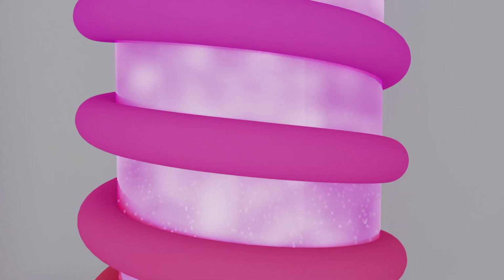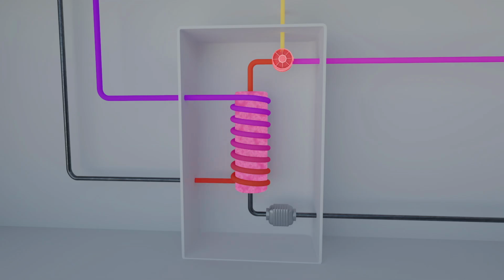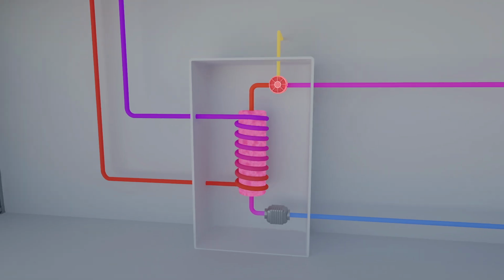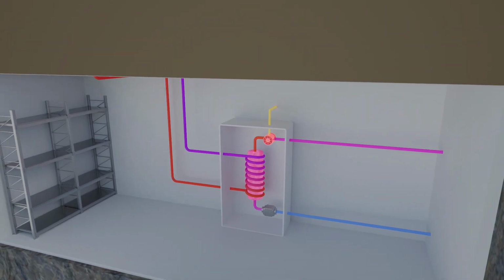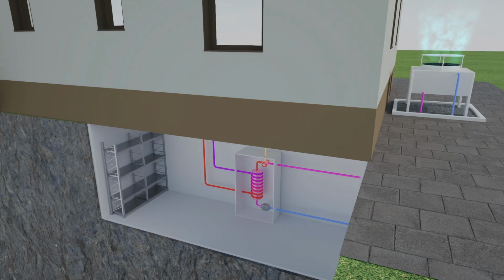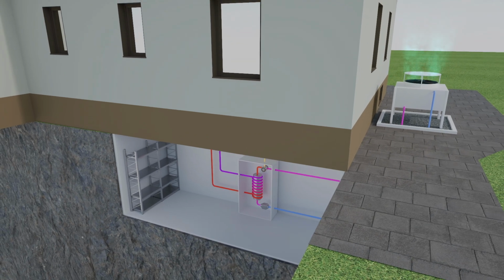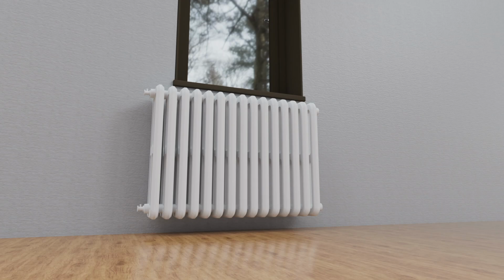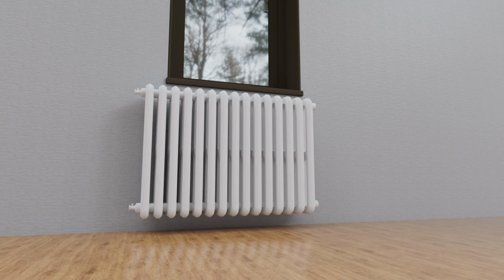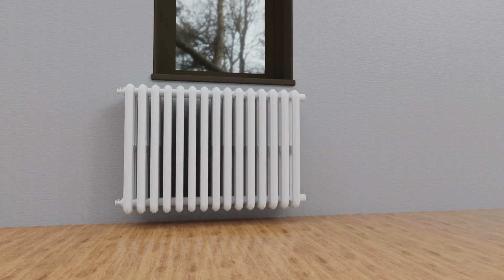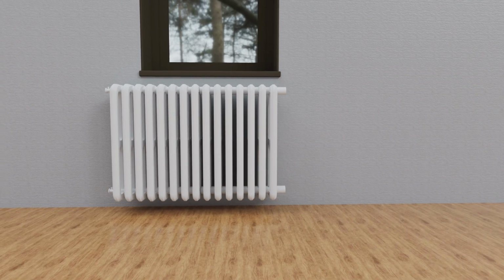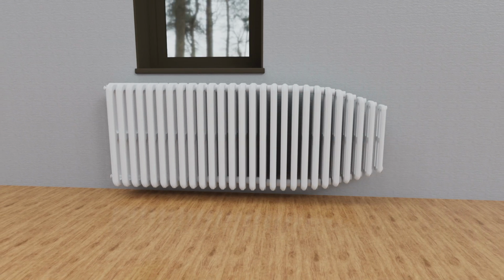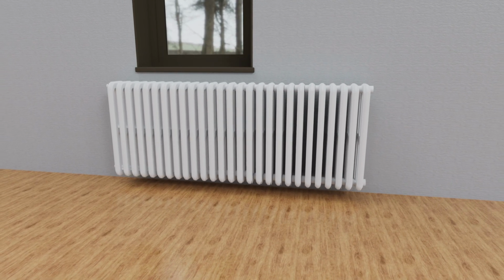The hot gas then transfers its heat to the heating water in the house via another heat exchanger. In the process, it condenses and flows through a throttle valve back to the outside for evaporation. Electrical energy is used to raise the ambient heat that surrounds us to an even higher heating level. The heat pump is particularly efficient when it generates a large amount of heat with as little electrical energy as possible. To do this, the heating temperature, that is, the temperature of the water inside the heating system, must be as low as possible, and that requires heating surfaces to be as large as possible.